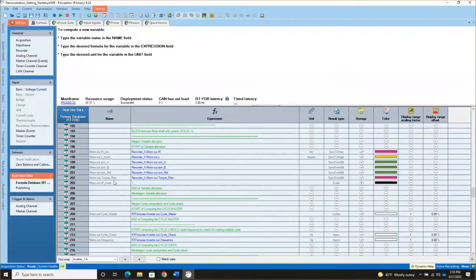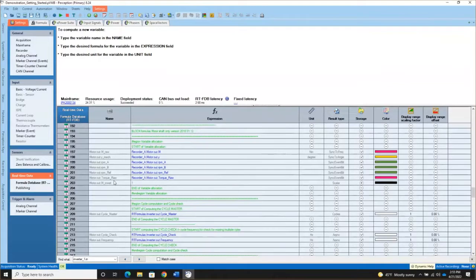In this case, I'm using a T40B torque transducer from HBM with a center frequency of 60 kilohertz. That means when the torque sensor is at zero torque, I'm seeing a 60 kHz pulse train; at maximum positive torque, I'm at 90 kHz; and at maximum negative torque, I'm at 30 kHz. What the timer counter channel of the power analyzer does is, for a specified window set by the user, watch that pulse train, determine a frequency, and then convert that frequency into the specified torque.